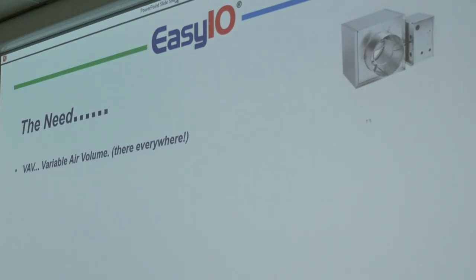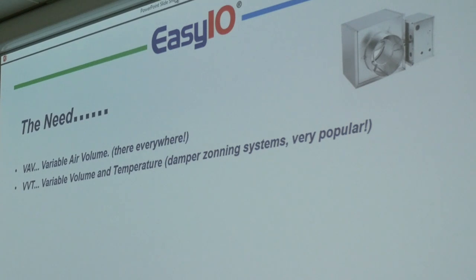So it's everywhere. There's not only new systems, but thousands of existing systems out there that aren't even DDC. They might be pneumatic. We have a lot of old buildings in the East where I'm from. And VVT, variable volume and temperature - those are the simple damper zoning systems, the systems that don't actually control to airflow, they just modulate a damper based on the temperature in the zone. It's basically a cheap poor man's VAV system. Those are very popular in the States.